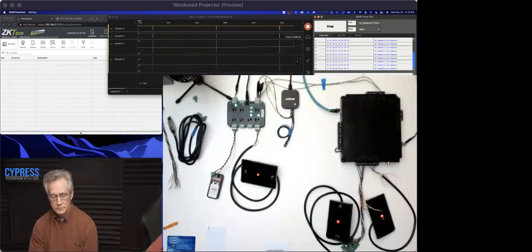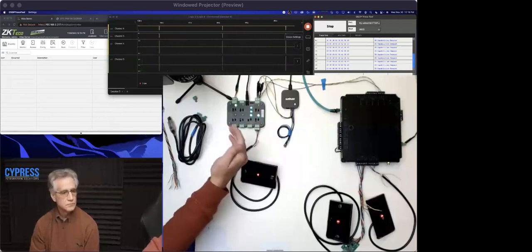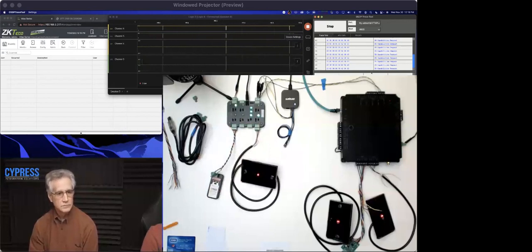So it's on the OSDP bus. It was powered on, but the 485 was actually shut off. And then we see that we're still getting a PD capabilities request. Correct. So that means that one of those three parameters is probably not set correctly.